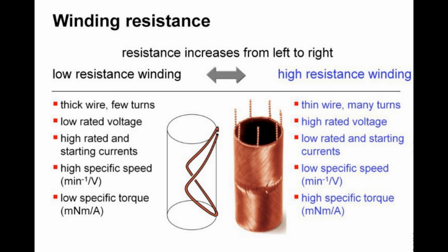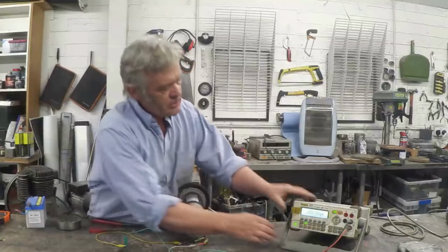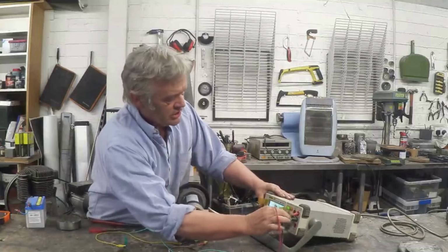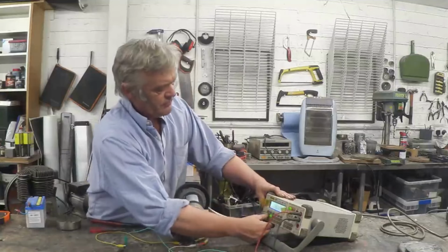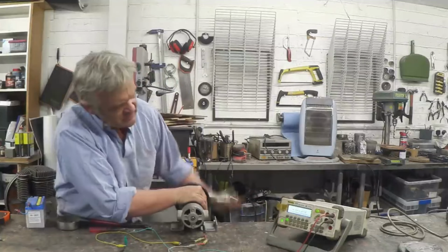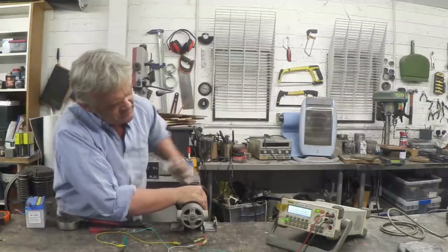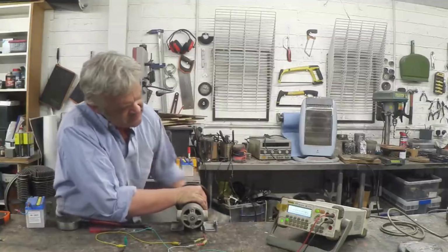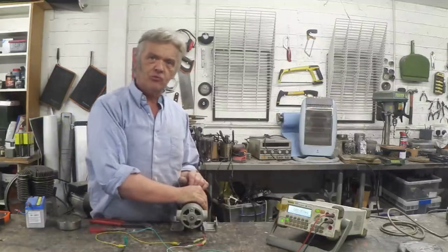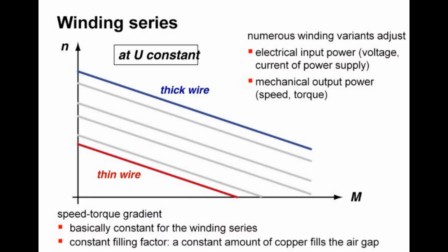Something has a high resistance, it means that it's very susceptible to load. So if we swap this onto the voltage, leaving it in closed circuit, remember we got about 3 or 4 volts at that range, and if I give it a turn now, we're hard pressed to get about 0.2 of a volt. So the voltage drops off dramatically, and that's a common thing that happens with high resistance, high torque motors.